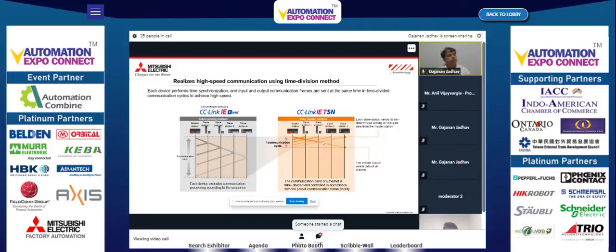This network depends on all stations being given particular time slots. Based on available time slots assigned to the nodes, they start communicating, so there is no concept of token passing. This is like a time-sliced network communication, where all nodes on the network are always synchronized, and based on the time given, they put their data on the network. That is why it is very fast, and a lot of bandwidth is available for everybody to share data. So you can share time-sensitive, critical or deterministic IO type data or motion data, and at the same time information data also can be shared because a lot of bandwidth is available on this network.